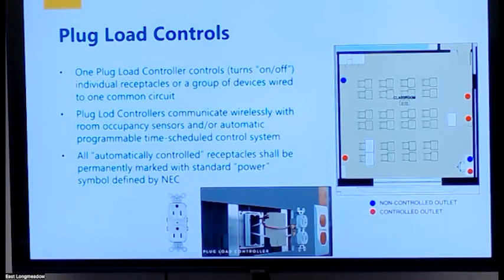But for the receptacles that are controlled, we're obligated by code to mark them so people are not confused and do not plug something that is actually critical into those devices. So there is a symbol by code, a little power symbol, so you see it on the receptacle. You know not to plug anything critical into this device because it's controlled somehow, whether by occupancy sensor or by time. Next page, please.